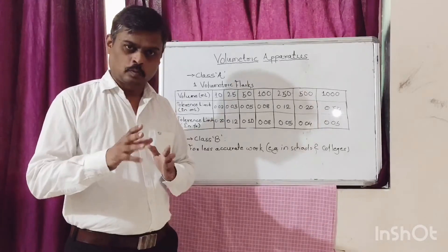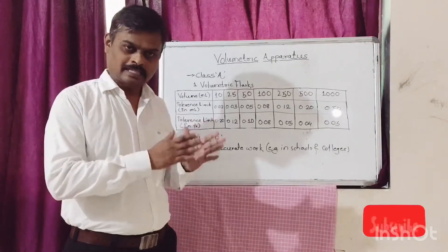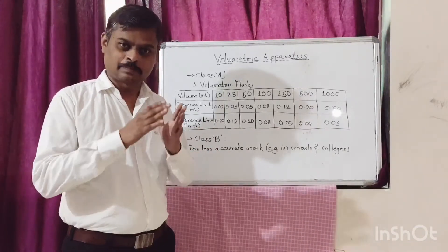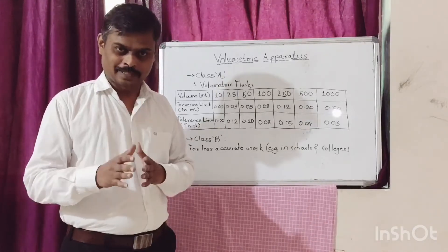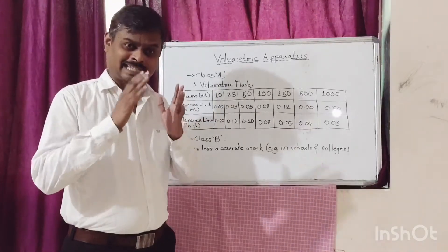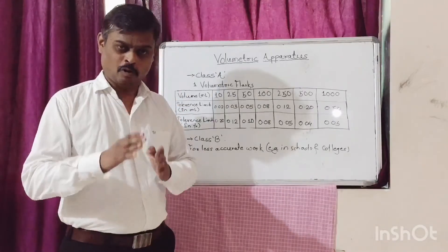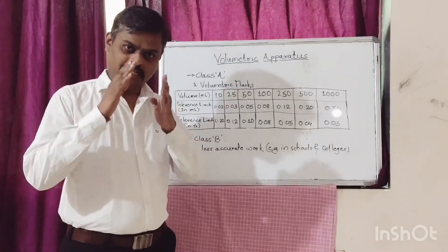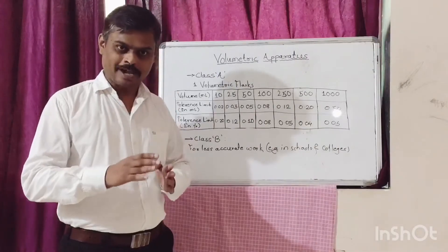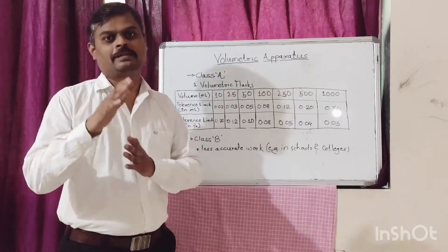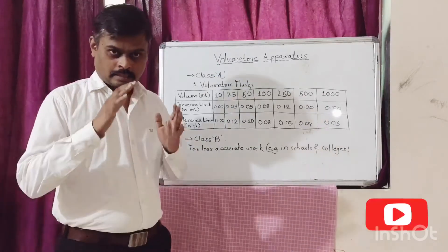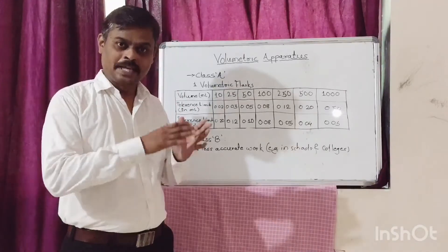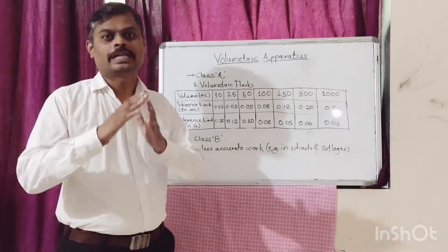There are 2 classes of volumetric apparatus: Class A and Class B. Unless otherwise specified in individual monograph or specification, Class A glassware shall preferably be used for analysis. Class A glassware is recommended for analysis which requires the highest accuracy and precision. Class A glassware comes along with a calibration certificate bearing a unique serial number or traceability.